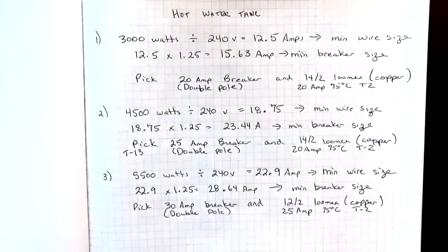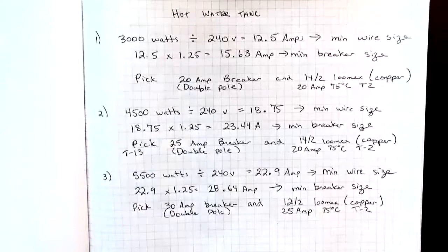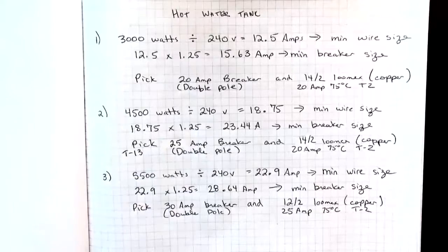Table 13 is our guide as to what the standard size breakers are. If you cannot get a 25 amp breaker in the particular brand that your panel is, then you could go to a 30 amp breaker. Again, this is a double pole breaker because of the 240 volts.